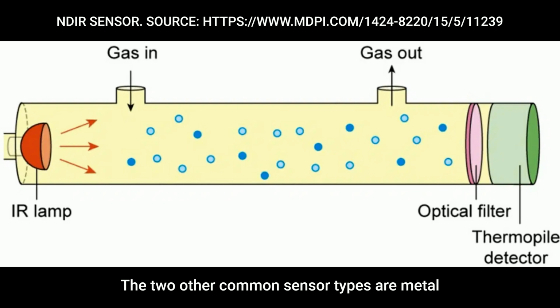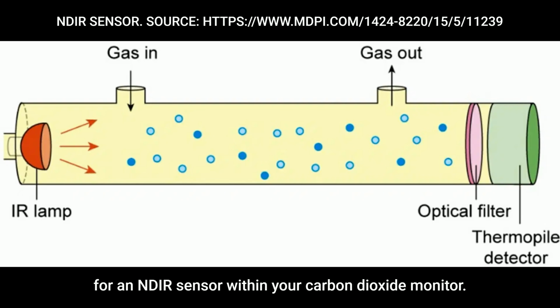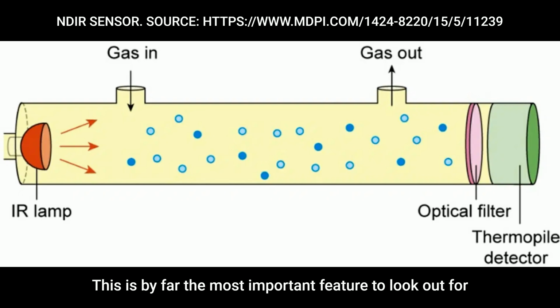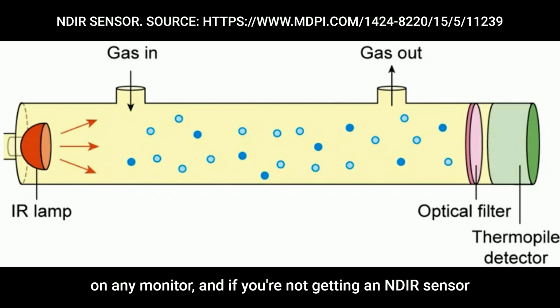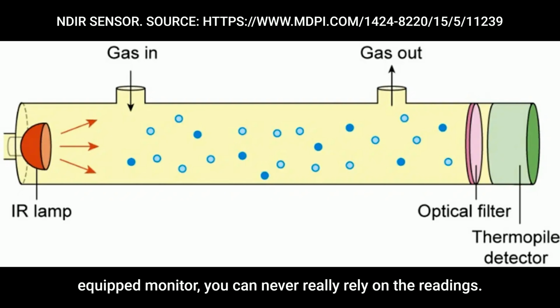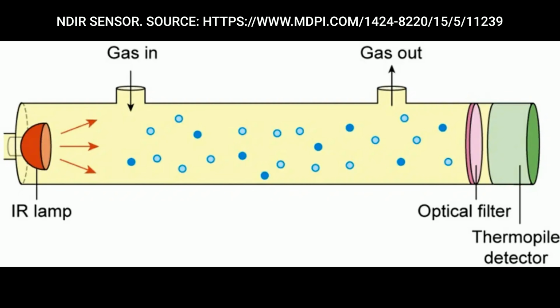The two other common sensor types are metal oxide semiconductors and electrochemical sensors. However, both of these sensors can be thrown off by other substances in the air that can impact readings. Furthermore, they tend to drift more than NDIR sensors, especially electrochemical sensors. For this reason, you'll always want to be on the lookout for an NDIR sensor within your carbon dioxide monitor. This is by far the most important feature to look out for in any monitor, and if you're not getting an NDIR sensor-equipped monitor, you can never really rely on the readings.